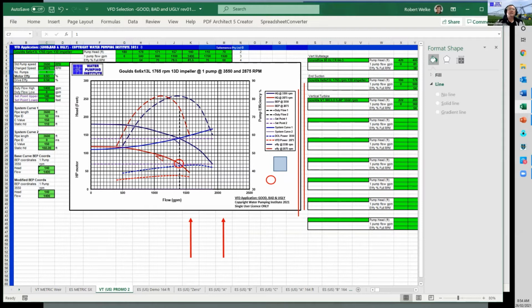Now, what happens when we do this? The power requirement goes down. The power requirement is now 38 horsepower, and the difference in horsepower between full speed and low speed is 41%. However, we've lowered the pump output by 50%, so theoretically we should be looking for a 50% saving. VFDs are sold by the cube rule: the power required is proportional to the speed cubed. Literally speaking, if you computed those speed differences, it would compute to that sort of saving, but it doesn't quite. We get a 50% head reduction and only a 41% pumping cost difference.